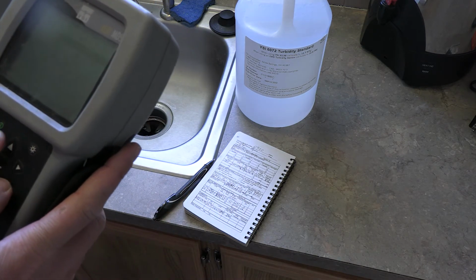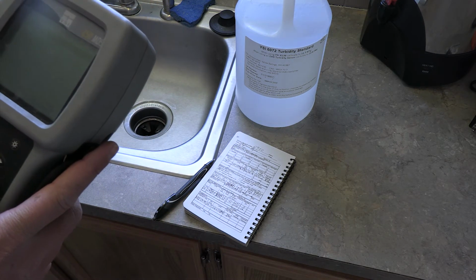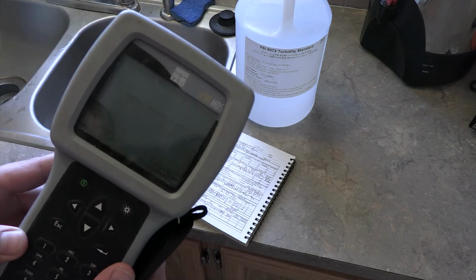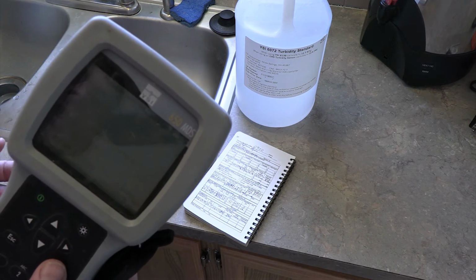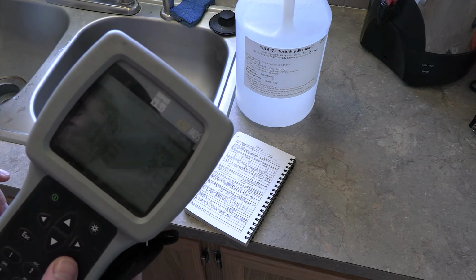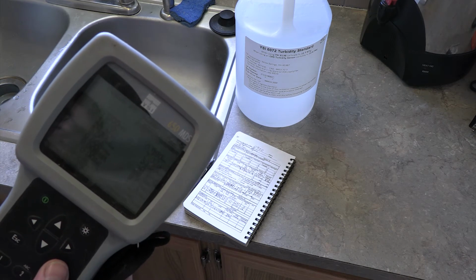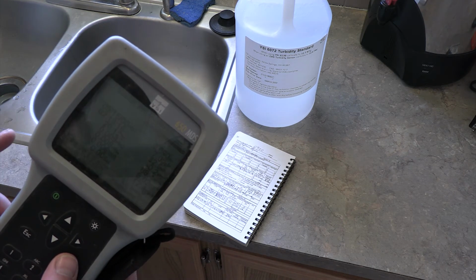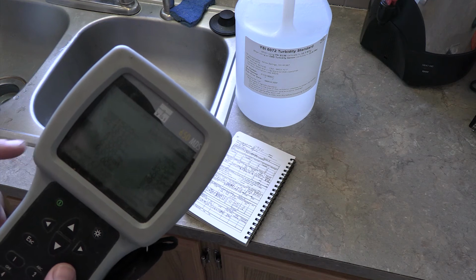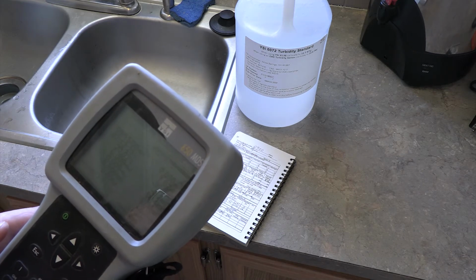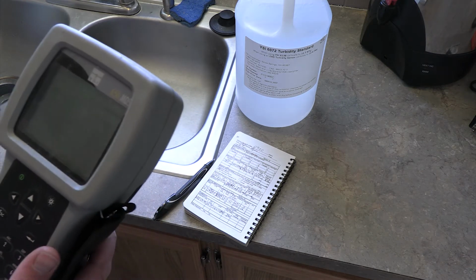Shoot. Way up. That's the issue we ran into. So we're going to go ahead and do a 1 point calibration first. Like I said, you can do a 1 point calibration at 0 with DI water, and then do a 2 point calibration. But your best bet is to do a 2 point calibration with 0 first, and then the YSI solution, and then go back and do a 1 point calibration with DI water at 0.8. That will give you a little bit higher number so that it won't go negative on you, because that will happen.